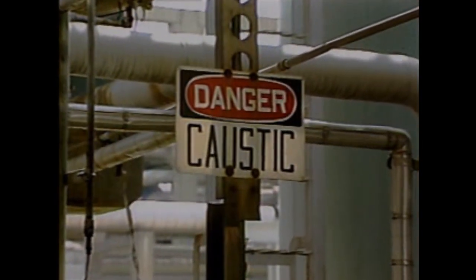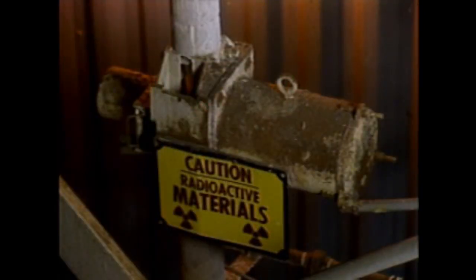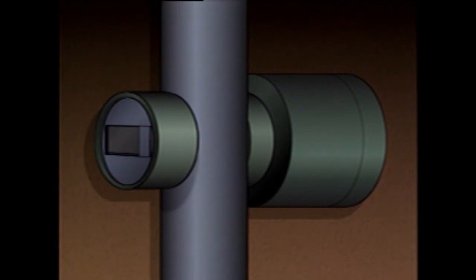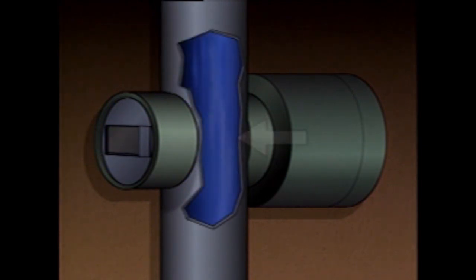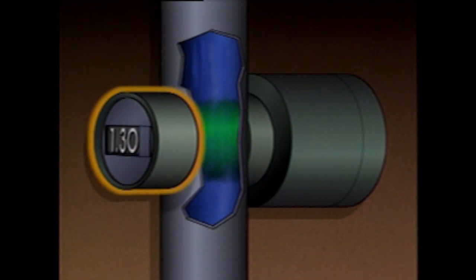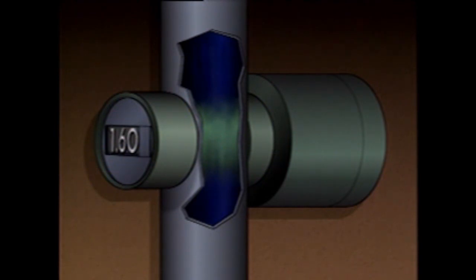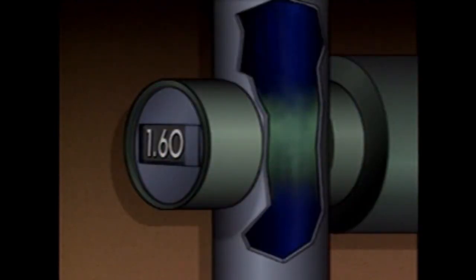Some process liquids are too corrosive for certain density measuring devices. In these situations, a radioactive density analyzer may be used. A radioactive density analyzer measures the density of a liquid without coming into direct contact with the liquid. During operation, a radiation source sends a small amount of radiation through a pipe containing the liquid being measured. The amount of radiation that reaches a detector on the other side of the pipe depends on the density of the liquid — the denser the liquid, the less radiation reaches the detector. The detector may display the radiation measurement as a density value or as a concentration value for a particular substance in the liquid.